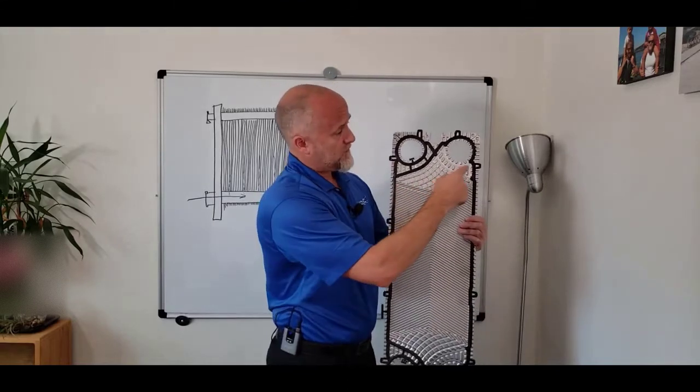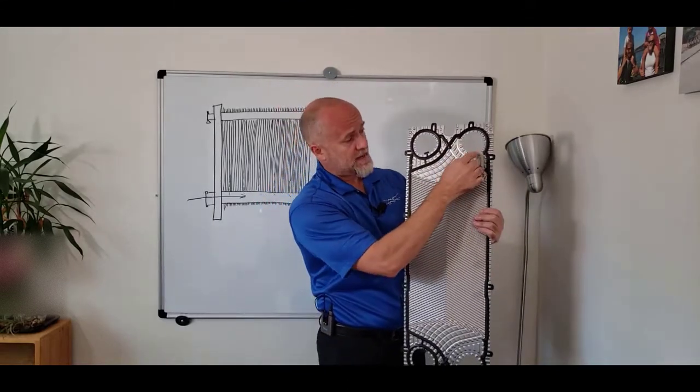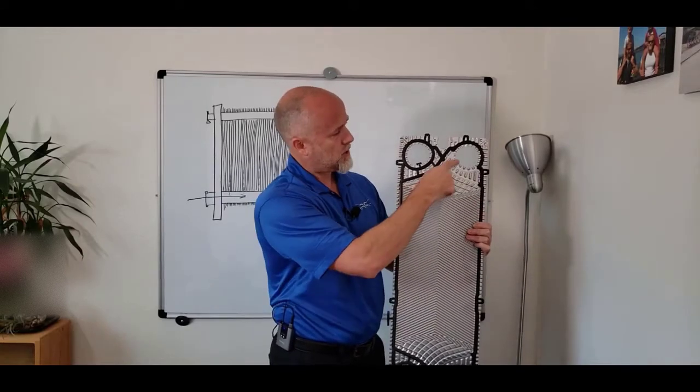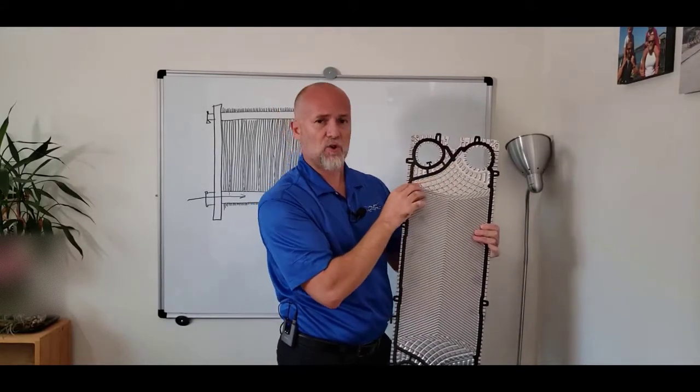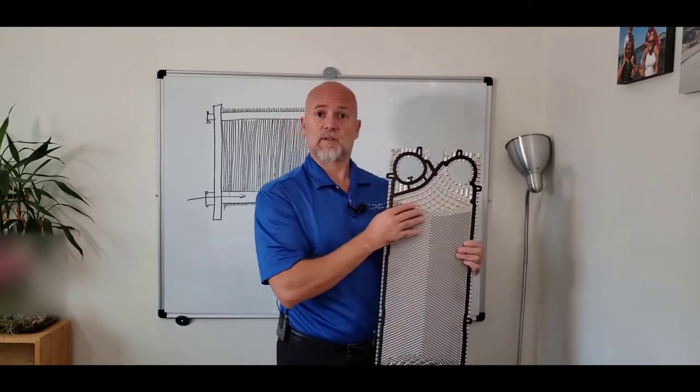A key aspect is you want to have a pressure drop of this path which is as equal as possible to the pressure drop of this path, so you don't have a path of less resistance and cold spots or hot spots that increase the chances of fouling. And this is exactly what this design does.